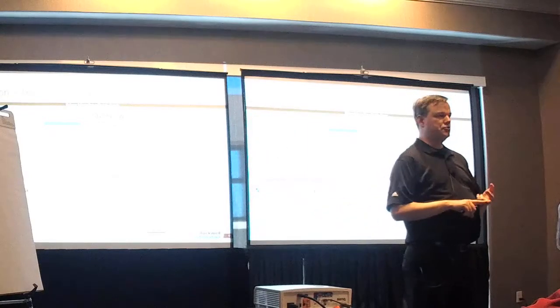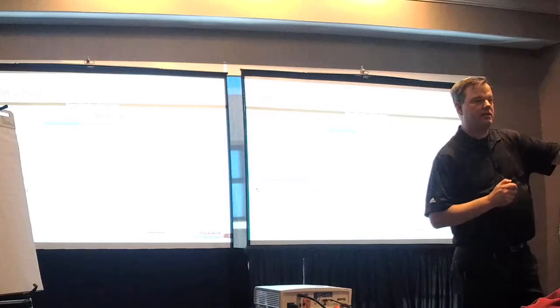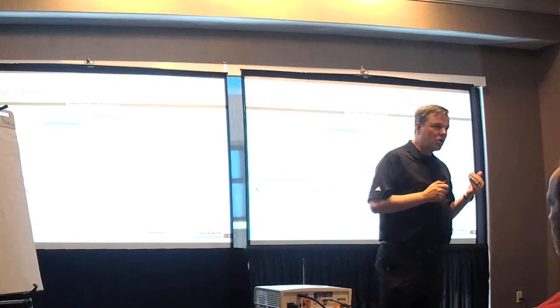Again, debugging and troubleshooting. How do we make an operator more effective, to not only know what's going on in the system, but be able to troubleshoot better? One of the advantages we're taking with the update to the HMI is an improved trending package, TrendPro. One of the nice things you see here is the leveraging of, say, discrete alarm conditions on top of the analog trend. So I know when a certain, say, 60 degrees here, my high alarm hit. Be able to see in reference where that alarm condition was met, when it was acknowledged, when it came out of alarm. Being able to layer that on top of the analog piece gives you more information to help make better decisions.